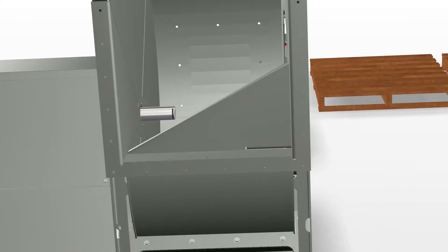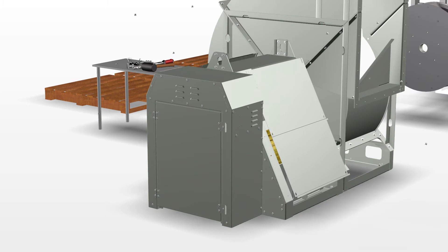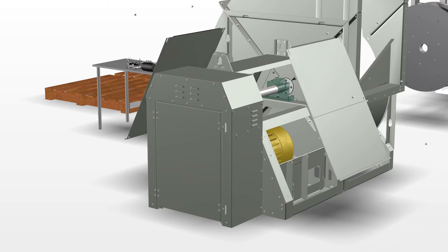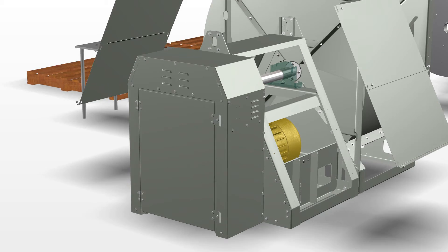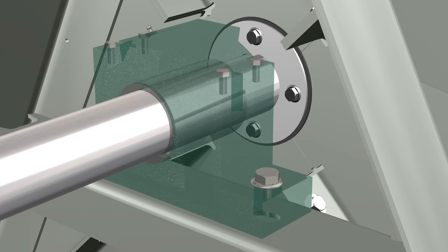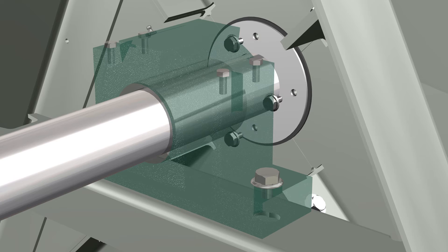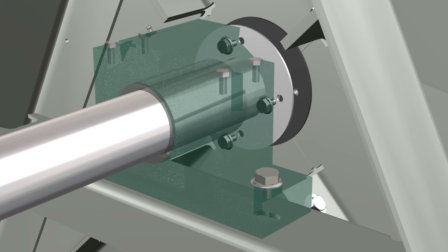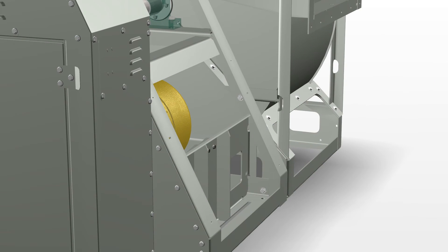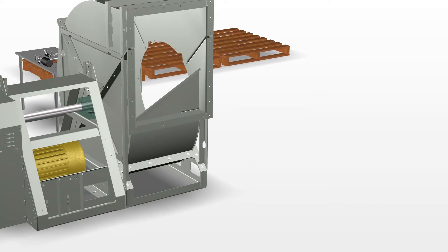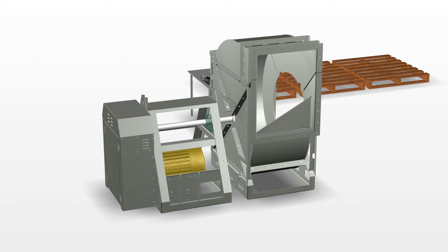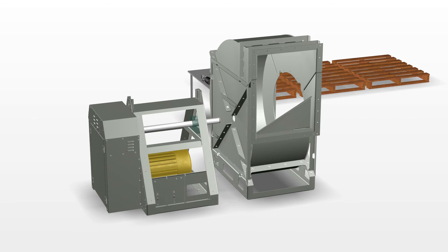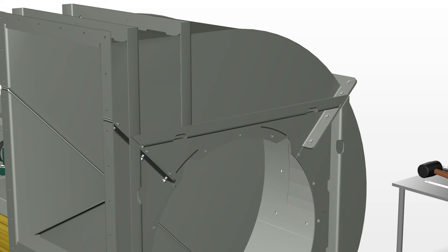To gain access to the bolts from the drive side of the fan housing, remove any weather hood panels if it has them. If there's a seal, you may need to unbolt it and slide it towards the bearing before you can proceed. Now you can remove the bolts from the pedestal to the housing and the isolation base. Separate the housing from the pedestal. Remove bolts from the split sections beginning at the top and place the sections on the skids. Be careful not to damage the parts.